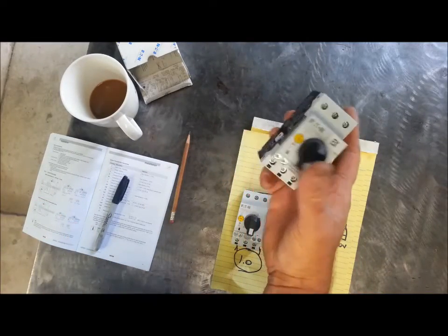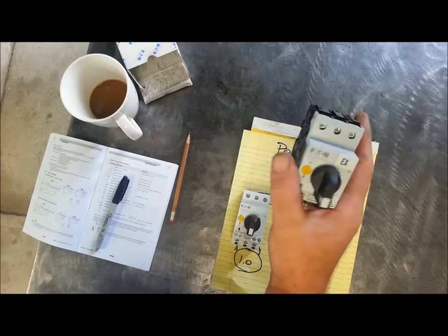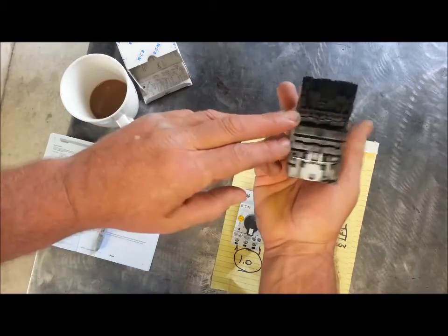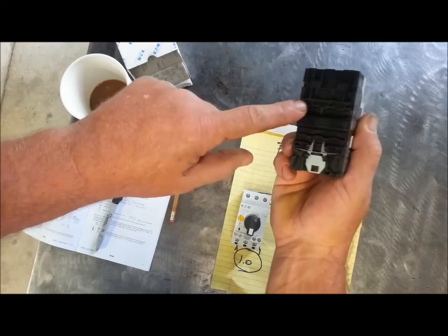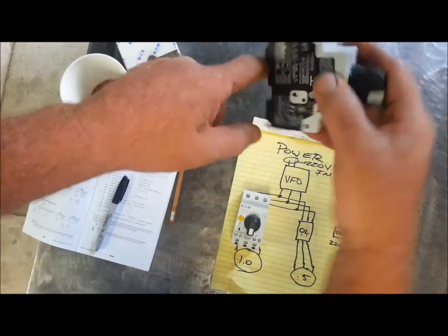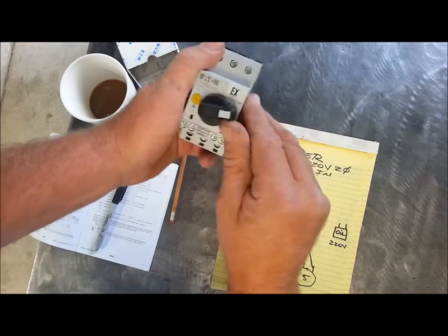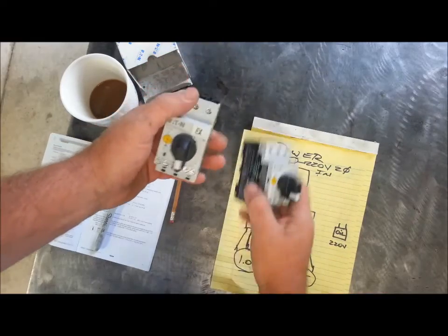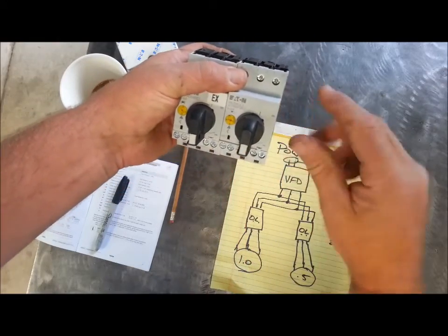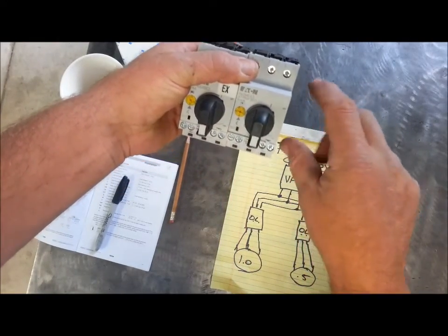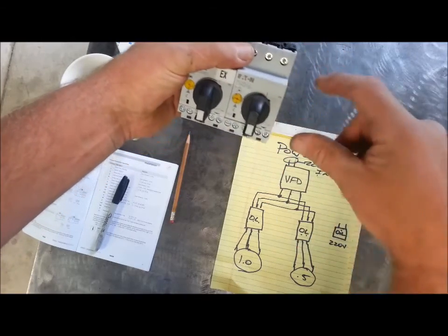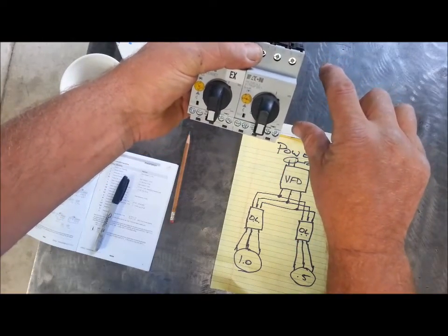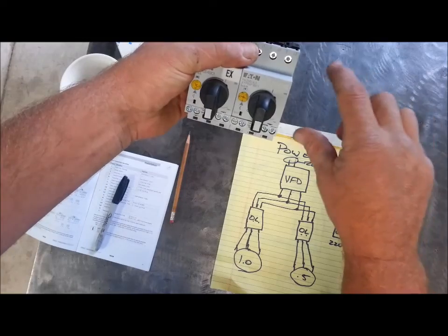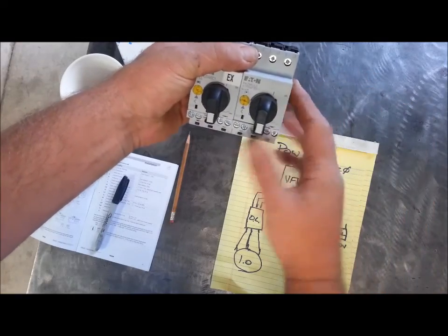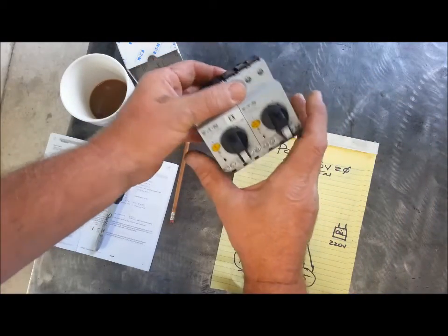But not high dollar. They need to be mounted in a cabinet because it's all open wiring. You can mount them on a DIN rail, which is the small aluminum channel. They just click, and they just snap on there. So you could do that, and you can also get fuse blocks that mount on a DIN rail. So you could have your two overloads and your DIN rail mounted in a Hoffman box or something with a couple of small fuses next to it. So you can keep it all very neat.